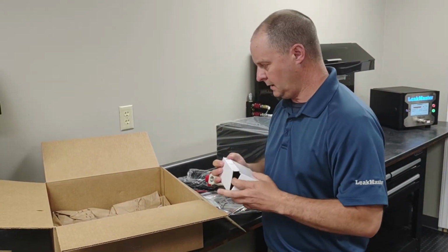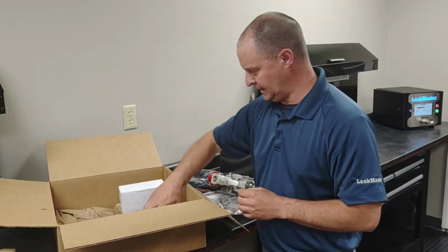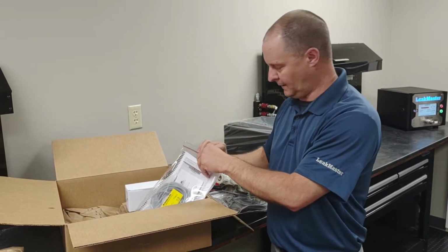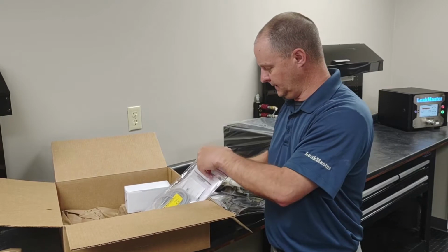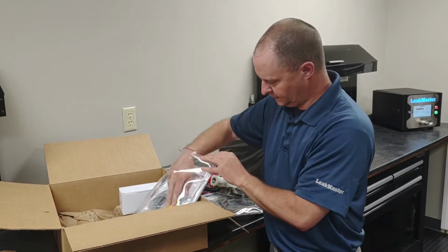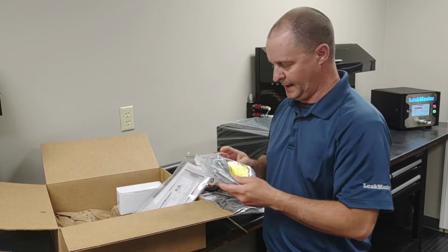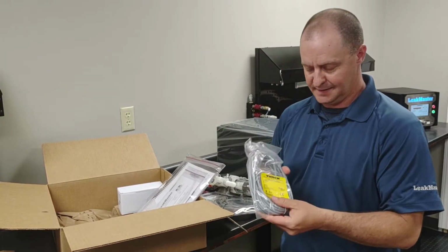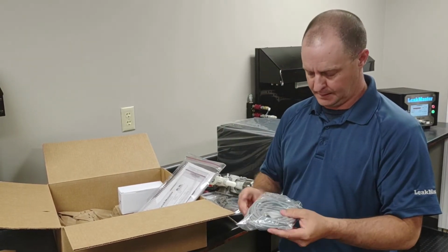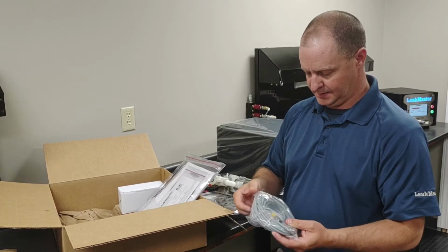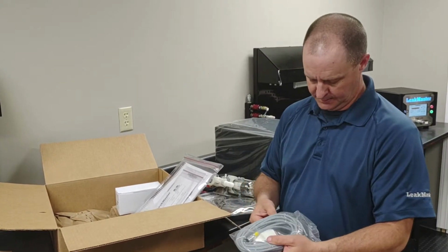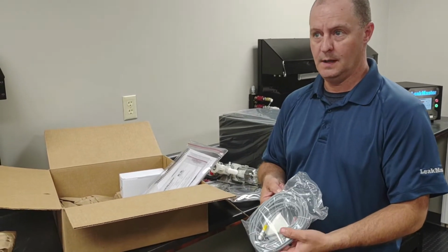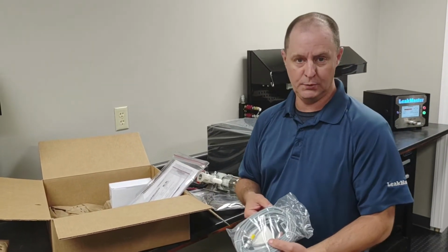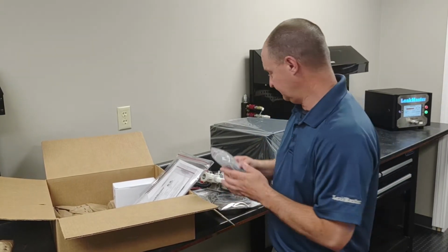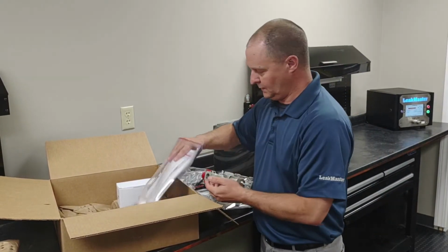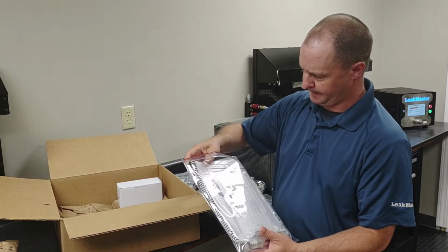If you are integrating or building a machine and you already have a 24 volt power supply on the equipment that you're building, you likely won't buy the 120 volt AC to 24 volt DC power adapter. So in that case, it's going to come with a Turck cable. This is what you would wire up to your power supply. You're going to wire the brown up to your positive 24 volts and the blue to your common. You're also going to receive a manual with it.